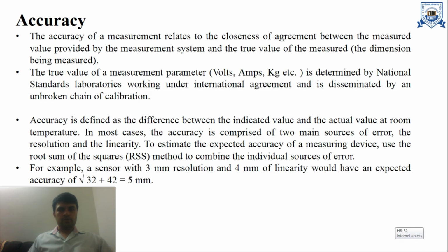In measurement terminology, the first term is accuracy. The accuracy of a measurement relates to the closeness of agreement between the measured value provided by the measurement system and the true value of the measured. The true value of the measurement parameters, which may be in volts, amperes, kilograms, etc., is determined by national standards laboratories working under international agreement and is disseminated by an unbroken chain of calibration.